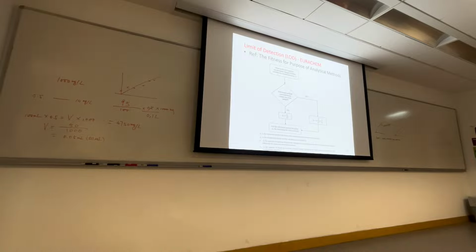So one very important point is the interpretation of n. N is the number of replicate measurements averaged when reporting the result, where each replicate is obtained following the entire measurement procedure. Normally, for most laboratories, when you repeat the measurement 10 times, they will say that n is 10. Is that right?